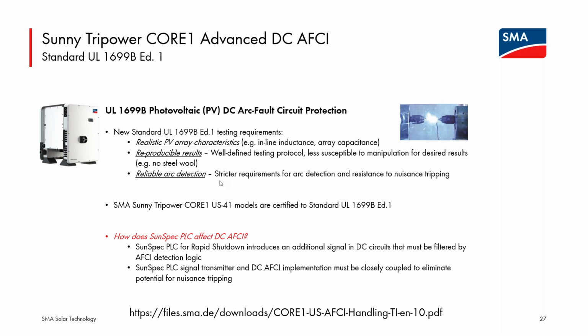Okay, I will close up on the AFCI option, and I will at least start on the PEAK3. I know we're kind of running up against time. The other functionality unlocked by the latest version of firmware for the US-41 models of the CORE1 is this: now that UL 1699B is a full published standard, it does allow in certain low energy, very quickly extinguished arcs, if an inverter, let's say the CORE1, detects an arc, an allowance for automatic restarting. Again, if that arc energy is under a certain threshold, and the arc can be extinguished within a certain time, then automatic restarts are allowed by the standard.